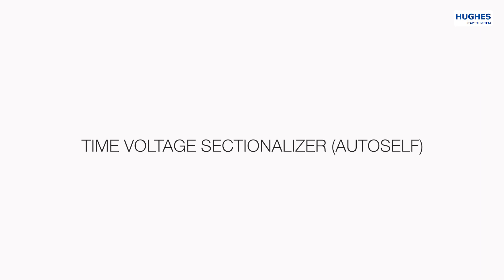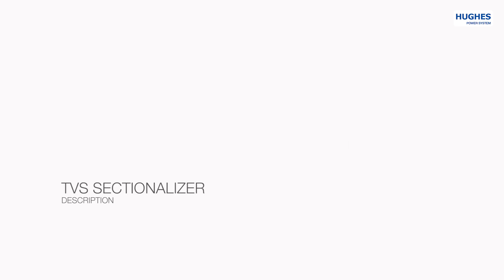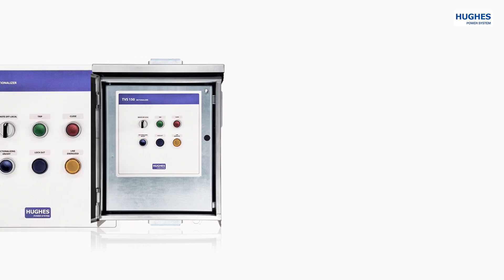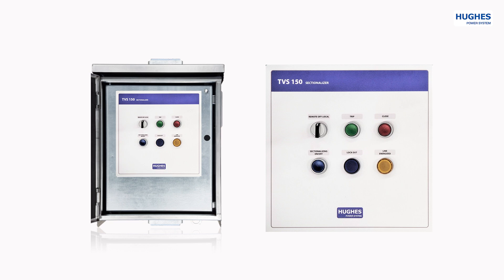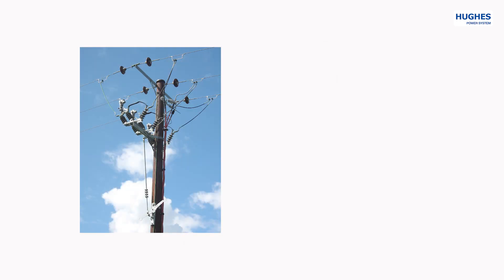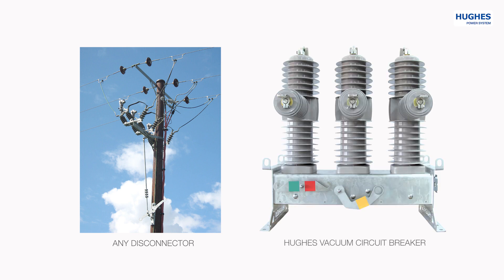What is a time voltage sectionalizer, how it works, and what are the benefits in comparison to a recloser? The time voltage sectionalizer is a control device for a disconnector or a load-break switch, with the purpose to automatically disconnect a faulty section of a distribution line. It is fitted into a cabinet with all necessary equipment like motor mechanism, batteries, optional communication equipment, etc. The only difference between AutoSelf for disconnectors and load-break switches is that the disconnector version contains an additional motor mechanism.